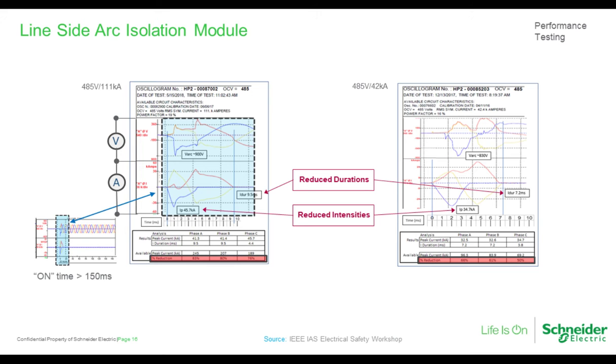The next thing is that the amount of let-through current is dramatically reduced. In this example, the peak let-through current of the 111,000 amp test was just 46 kiloamps out of a prospective 245 kiloamps, representing an 80% reduction. This is because the 800 plus volts of arc is designed to emulate a current limiting circuit breaker, very similar to about an 800 amp current limiting circuit breaker. The performance at 42K is a little less impressive, but still remarkable.